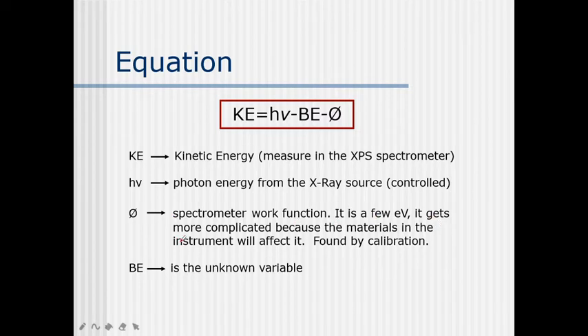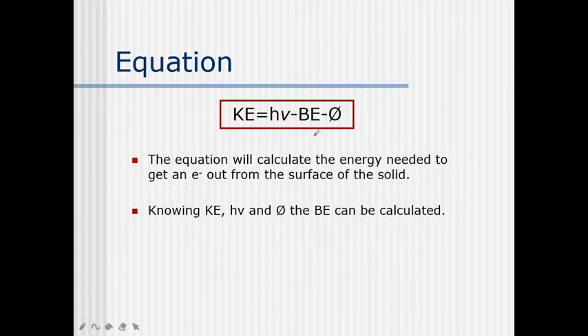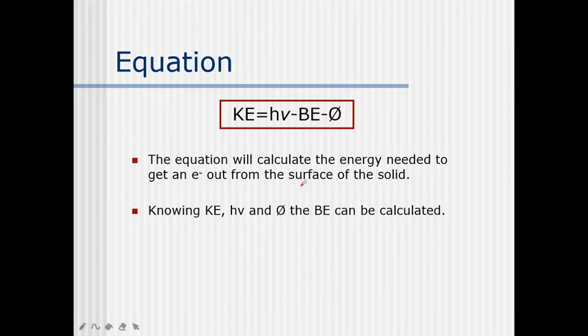φ is the spectrometer work function, which is a few electron volts. It gets more complicated because materials in the instrument affect it, and it is found by calibration — different materials have different work functions. Binding energy is the unknown variable; it is what we want to know. Knowing KE, hν, and φ, the binding energy can be calculated. This equation gives the energy needed to get an electron out of the surface of the solid.